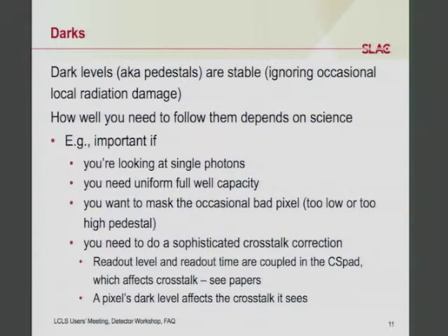So you're implying that you should take darks frequently. The crosstalk doesn't change. Well, if you're in a stable situation, you can take one dark, but you need to know about the dark if you want to do this.